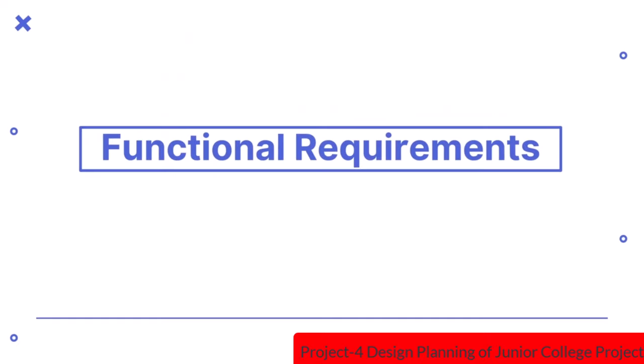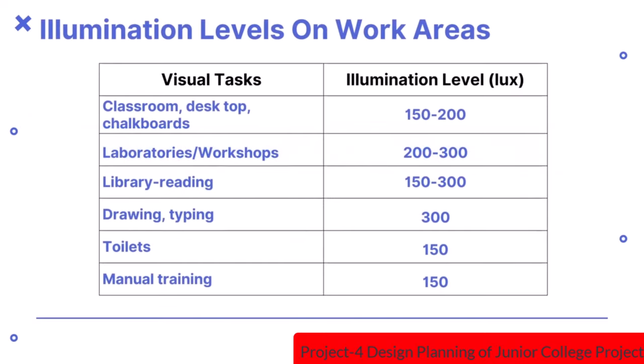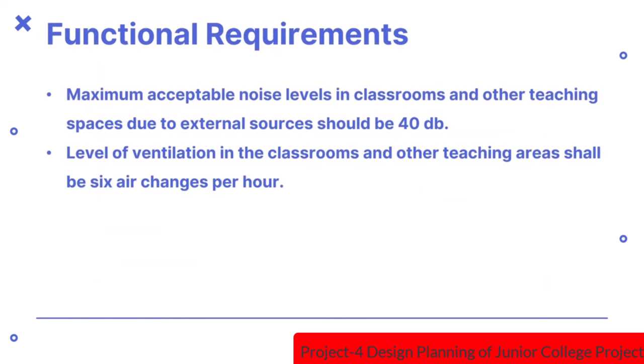Let us discuss the functional requirements of school buildings. Illumination levels for classrooms on desktops and chalkboards should be 150 to 200 lux. The maximum acceptable noise level in classrooms and other teaching spaces due to external sources should be 40 decibels. The level of ventilation in classrooms and other teaching areas shall be 6 air changes per hour.